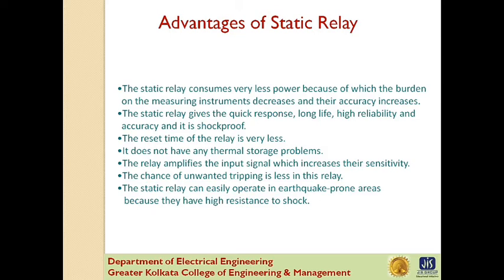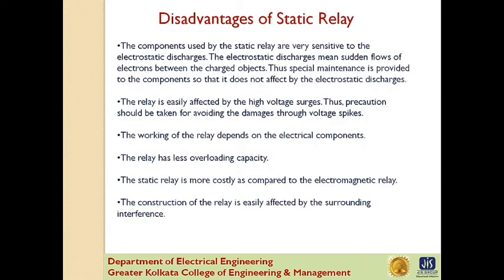Fifth, the relay amplifies the input signal which increases its sensitivity. Sixth, the chance of unwanted tripping is less in this relay. Seventh, the static relay can easily operate in earthquake-prone areas because it has high resistance to shock. And what are the disadvantages of static relay?